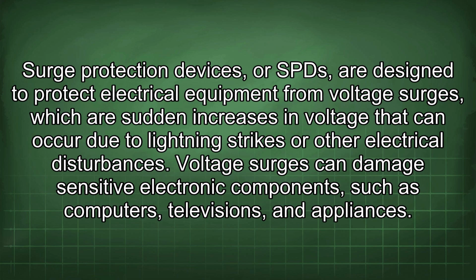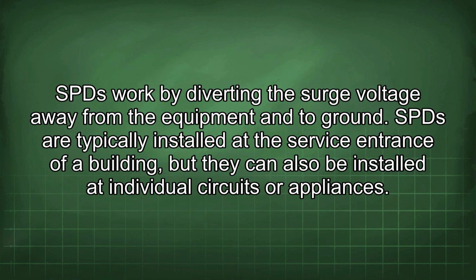Surge protection devices, or SPDs, are designed to protect electrical equipment from voltage surges, which are sudden increases in voltage that can occur due to lightning strikes or other electrical disturbances. Voltage surges can damage sensitive electronic components, such as computers, televisions, and appliances. SPDs work by diverting the surge voltage away from the equipment and to ground.